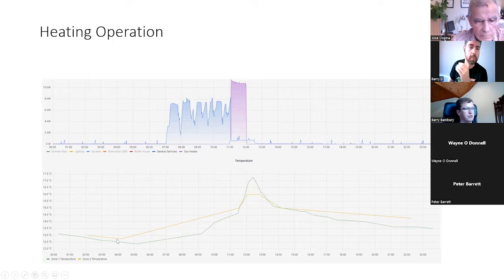We can see here temperature dropping throughout the night as temperatures get colder. We have a tiny bit of solar gain happening here as the sun rises and it's getting a little bit warmer. The air source heat pump comes on around 7 o'clock. So we're starting off here at 13 or 13.5 degrees Celsius. The air source heat pump runs for 4 hours until about here, but it's only able to increase the temperature of the church up to about 14.5 degrees Celsius. And if people are about to arrive in, it's not acceptable.